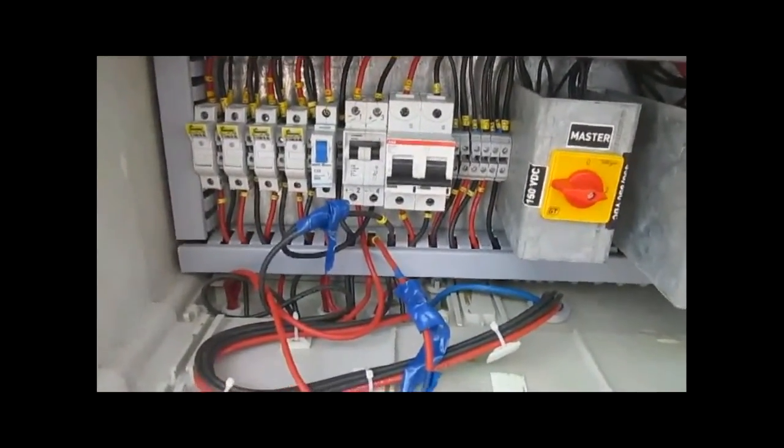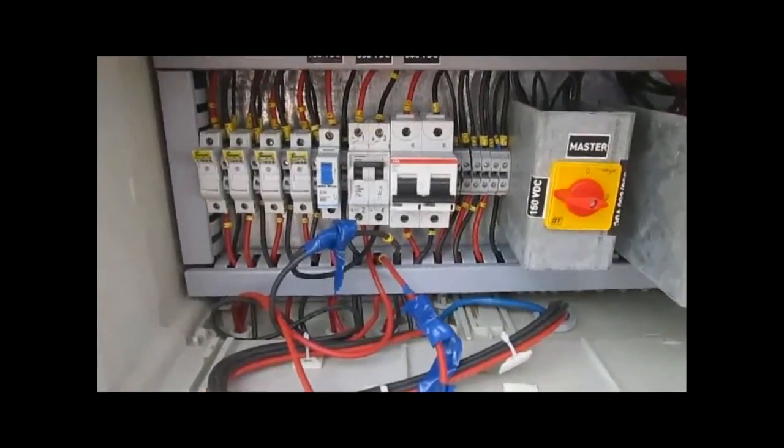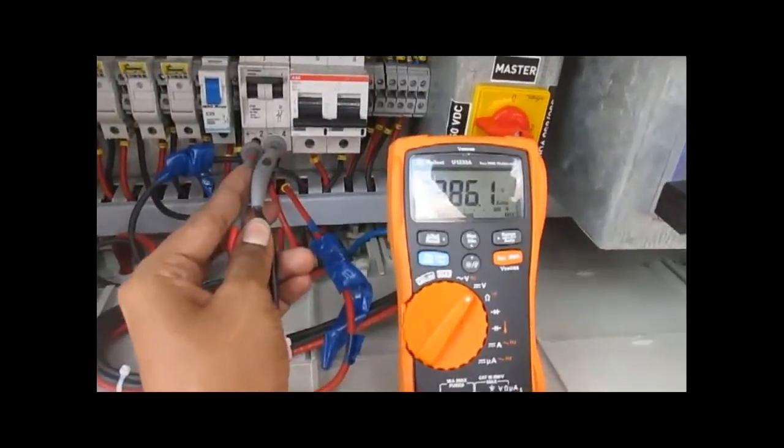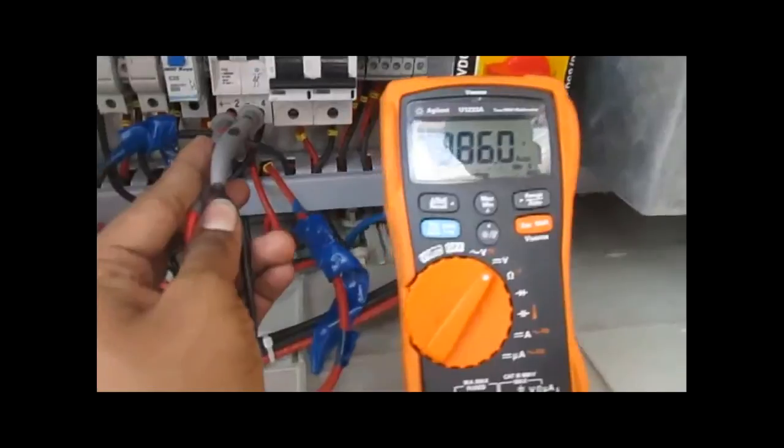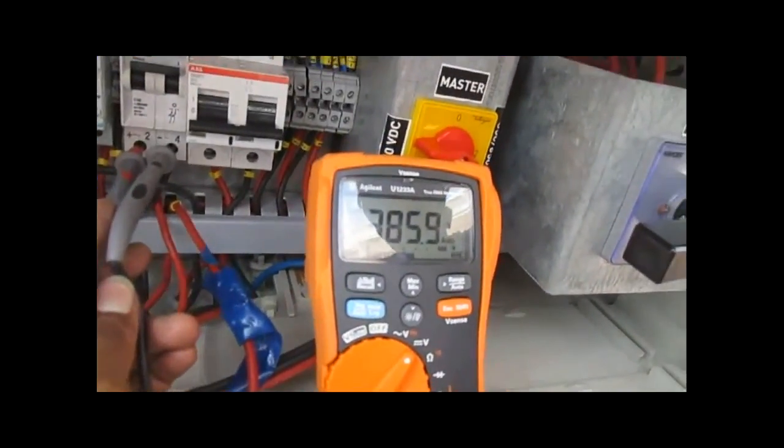The open circuit voltage for the 2.4 kW PV system is 380V DC which you are watching right now. You are also watching the irradiation, analog wind speed as well as the temperature.